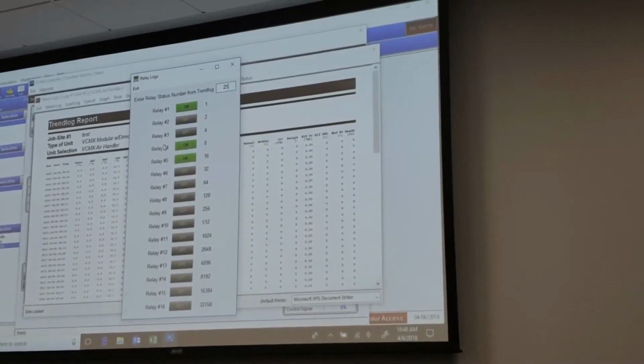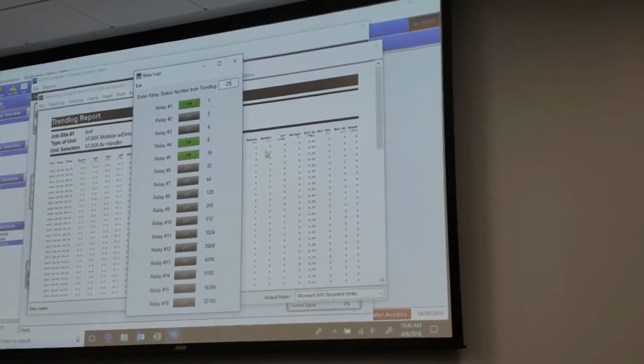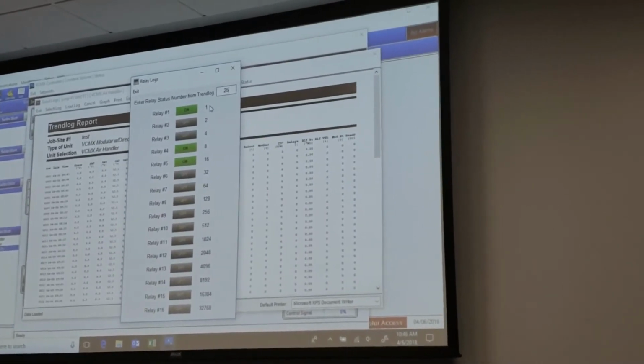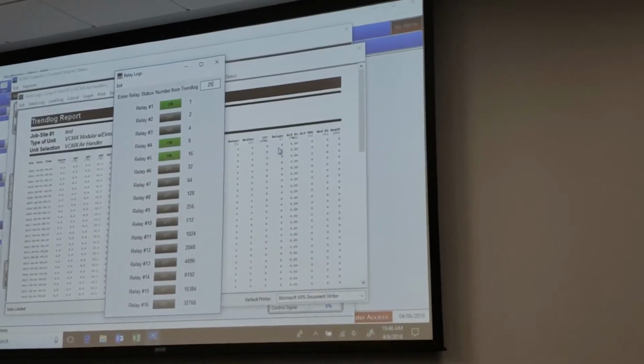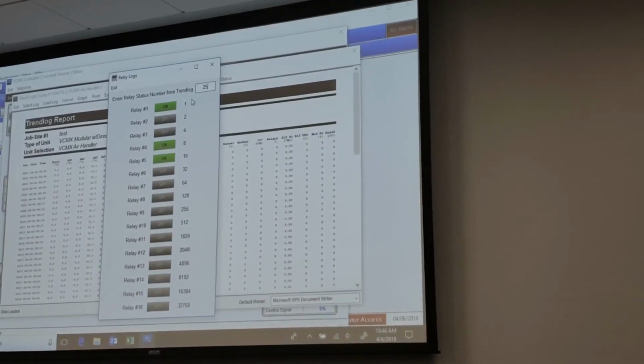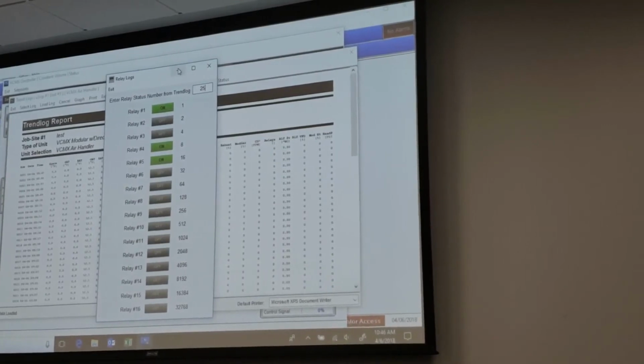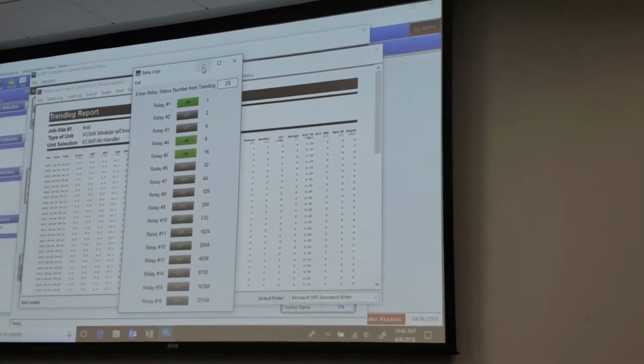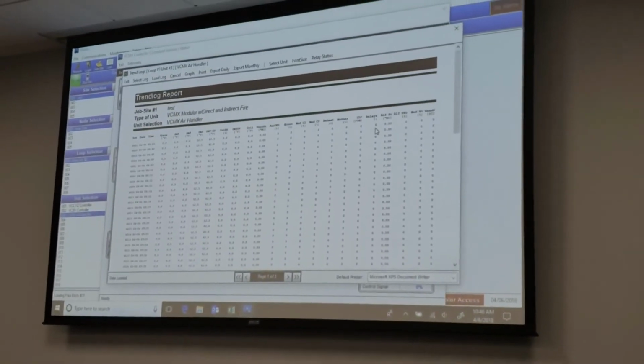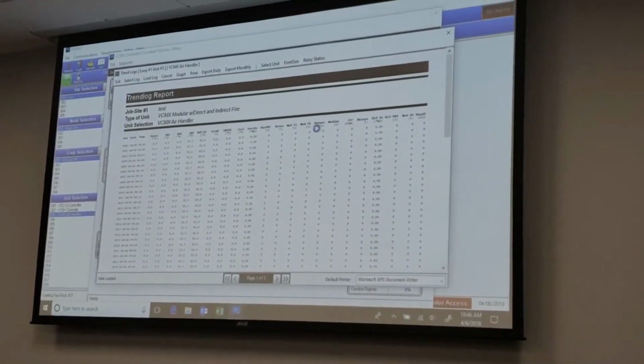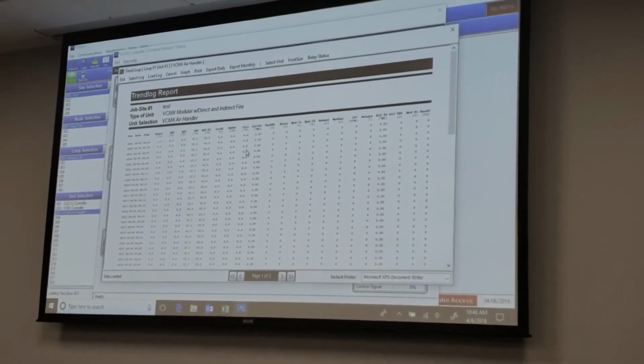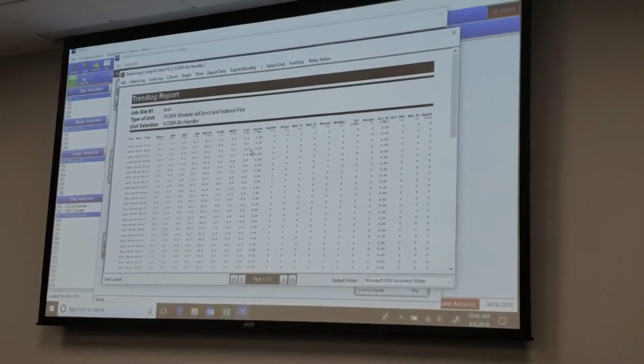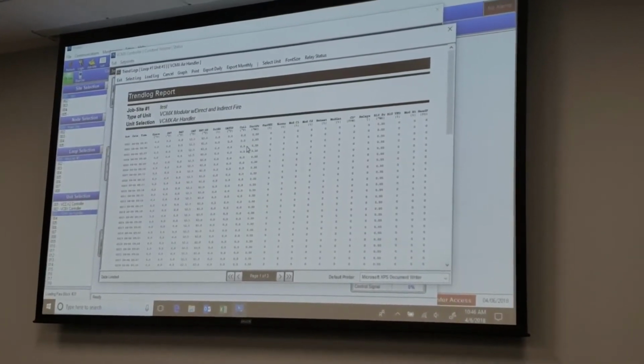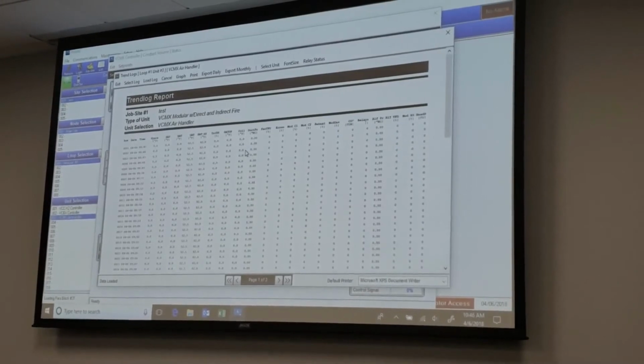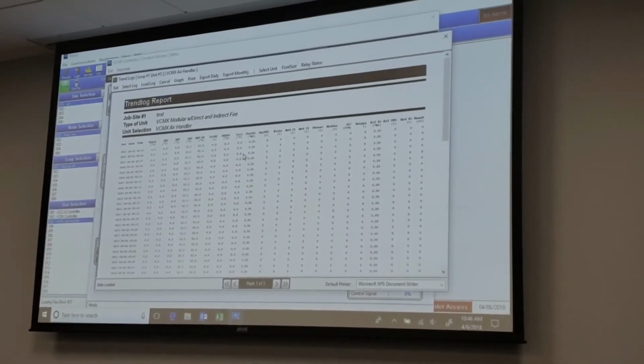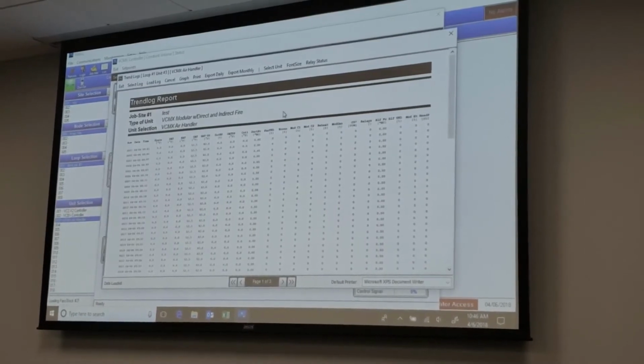Let's say these are your cool stages. So at that particular given time, the fan was running, because fan is always number 1, and the 2 stages of cooling were calling, they were running. Now I can take that information, but you got to use some deductive reasoning with this. If I knew that my compressors were calling, but I'm looking at my coil temperature and it shot up, then that tells me my compressor shut off, because coil temperature went up. Why did my compressor shut off? I was always calling for it to run. Something mechanically happened with it.